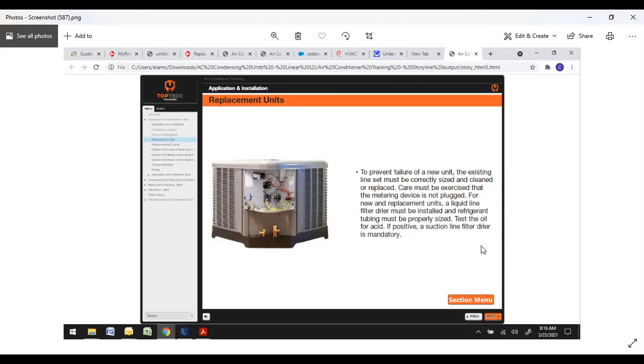If you're going to use existing line sets, do test the oil for acid. If it is positive, a suction line filter dryer is mandatory to catch any acid and debris. Obviously, you'd want to treat it for acid before you even go that far. If you do have to install a suction line filter dryer, remove it after 72 hours. Don't leave it on there. It can become an additional metering device over time.